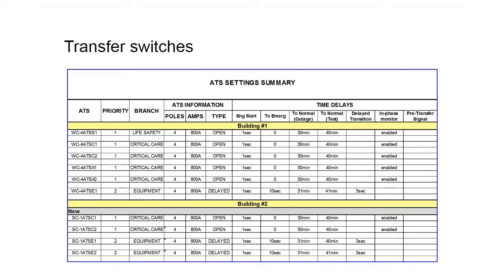And I've got an example here of a transfer switch schedule. I think the key things to take away here are the priority designation that I had indicated previously. The code required loads are obviously priority one. The optional loads, equipment branch loads, start to become different prioritizations. And what you're trying to do here is really to stagger the loads as they're added to the system. So your priority one loads by code have to be online within 10 seconds.